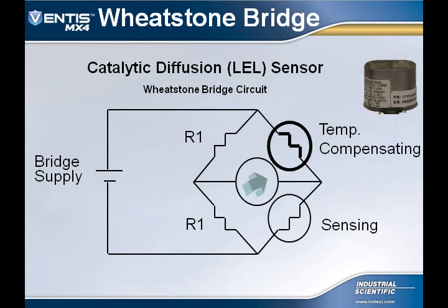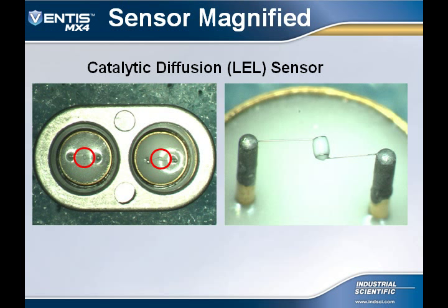This is the temperature compensating bead in the Wheatstone bridge circuit. This is the sensing bead in the Wheatstone bridge circuit. These are the 2 fixed resistors that are located in the instrument. As previously mentioned, the sensing bead will increase in temperature as it burns the combustible gas as it enters the sensor. This is an actual picture of the LEL sensor showing the sensing and compensating bead.